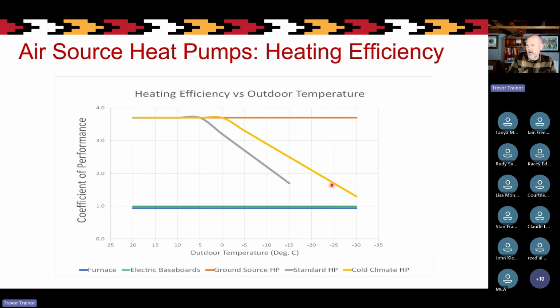Once we get down to about -25, it'll still be a coefficient of performance of about 1.5. So still 50% better. And so you can see that depending on how many hours of the year you have below -20 or below -25, the use of a cold climate air source heat pump can still save a lot of energy compared to using a furnace or electric baseboards to heat your home.